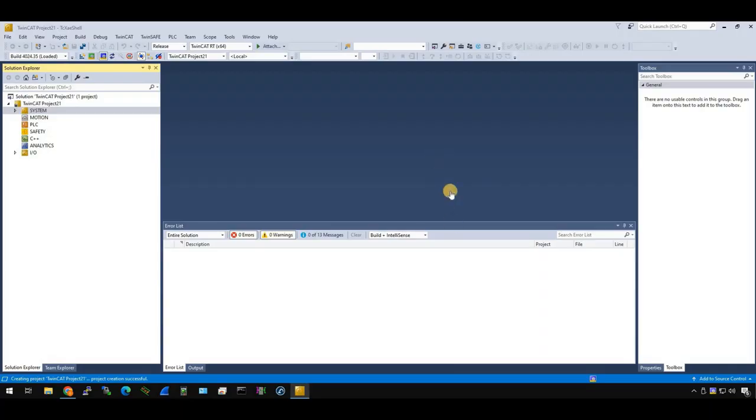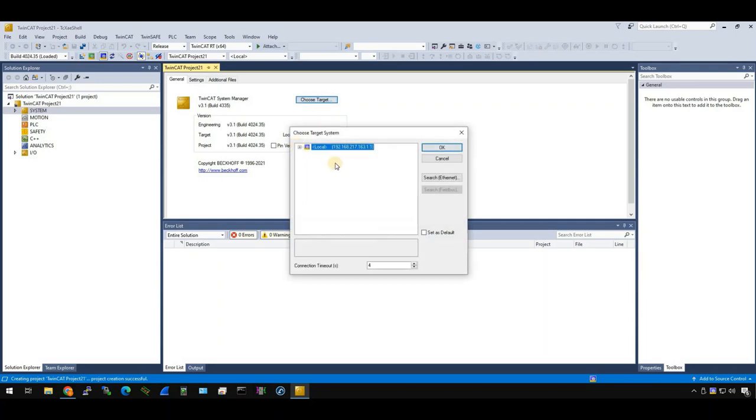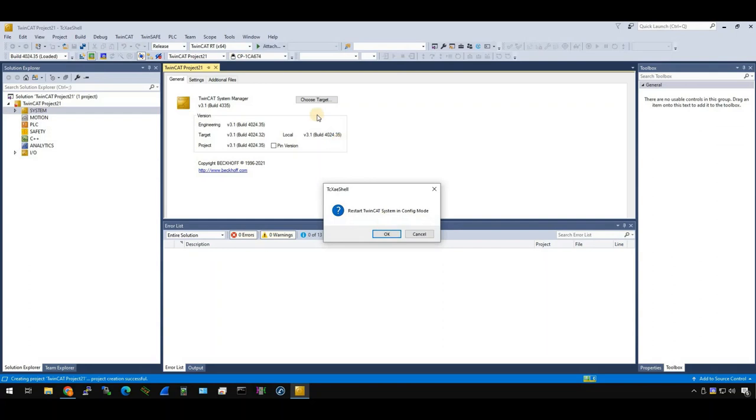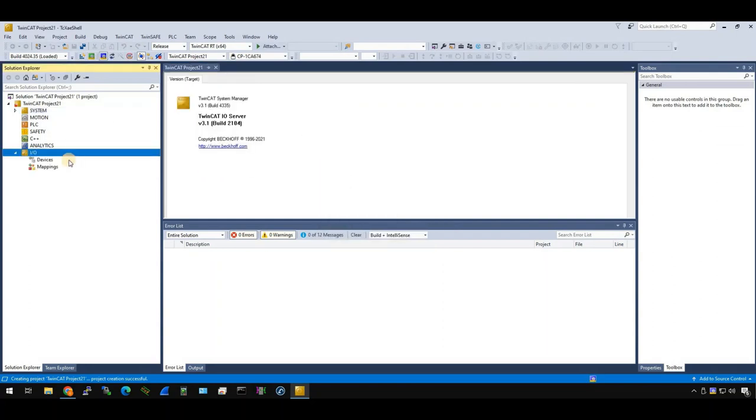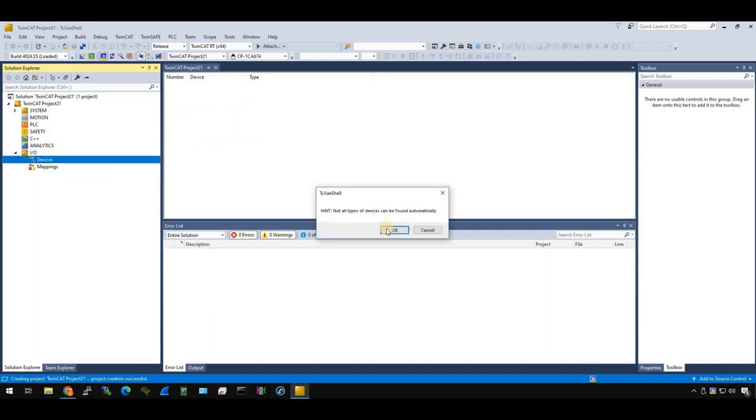Okay, now it's the time to configure our TwinSafe project. First of all, we need to make sure our connection between our PC to IPC is connected. Go to system and choose target and browse. Now you can see we have a connection between my TwinCAT system, my TwinCAT IDE to the IPC. That's okay. And first of all, we need to switch our IPC to config mode.